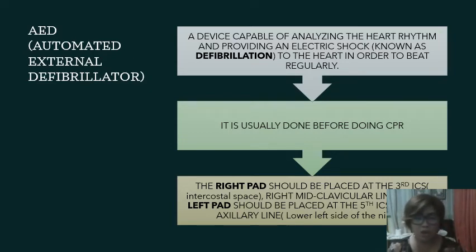So the positioning of the pads is very important in order to sandwich the heart once the device gives its shock. The heart has to be in the middle so that the shock will be given directly to the heart. Okay, so proper placement is very important.